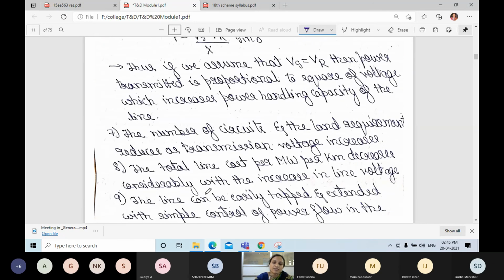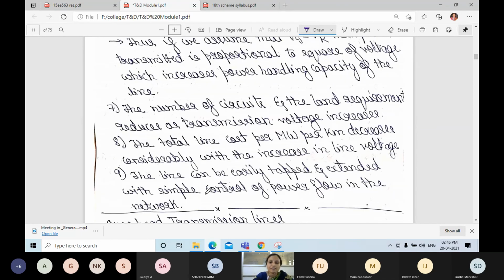Next, the number of circuits and the land requirement reduce as transmission voltage increases. This is also an advantage. The total line cost per megawatt per kilometer decreases considerably with increase in line voltage. If you increase the voltage level, the total line cost per megawatt per kilometer also decreases, and land requirement also decreases, and it can be easily tapped and extended with simple control of power flow in the network.